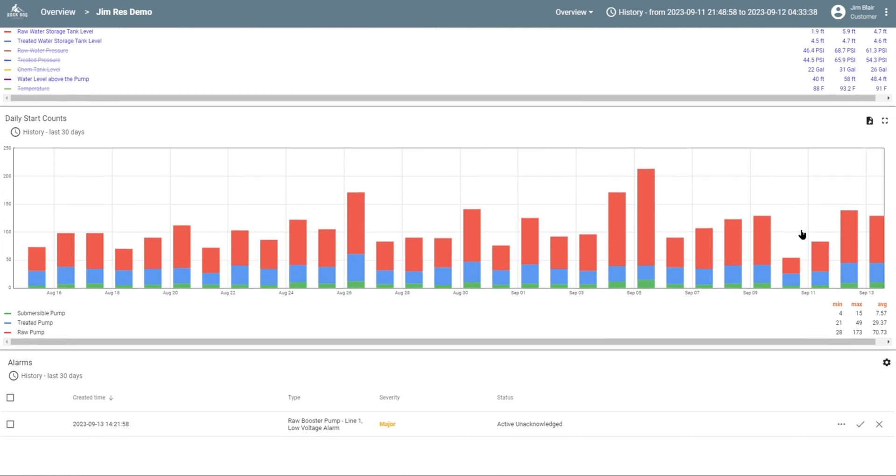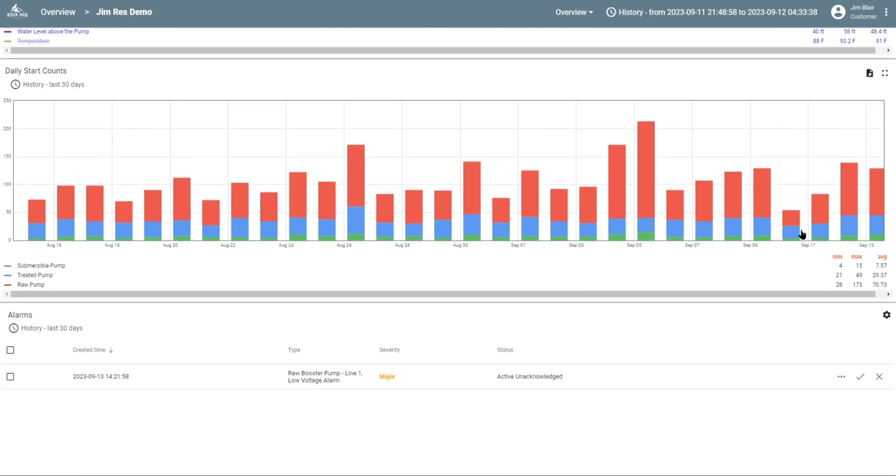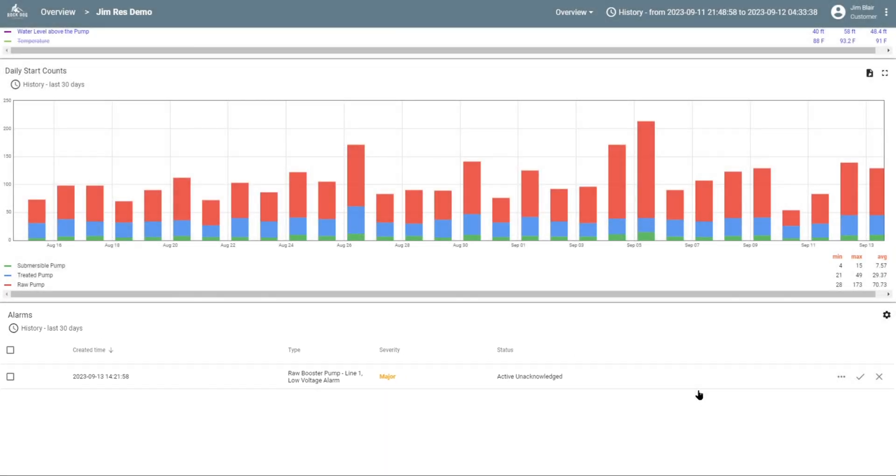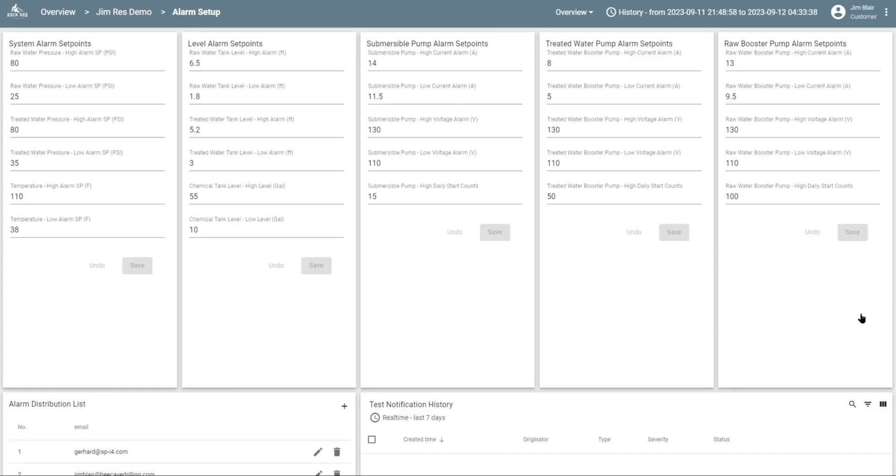Down below the start count, we see the alarms. The alarm we see here is the alarm we created when we turned off the power to that pump. The alarm will only come once so it doesn't bug you every minute that something is wrong. It won't come back on until you acknowledge the alarm and clear it out. If we click on the gear icon here, you can see that we can set up any alarm for any condition. If the value is too high or too low, we will let you know right away.